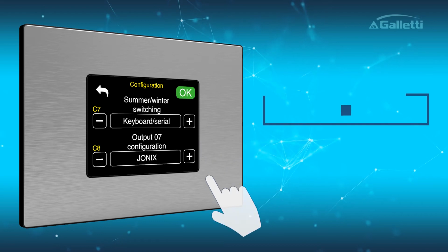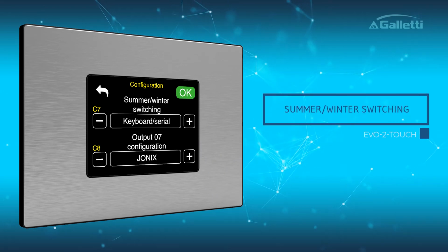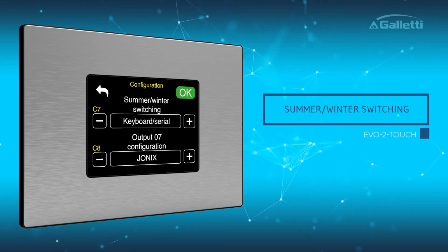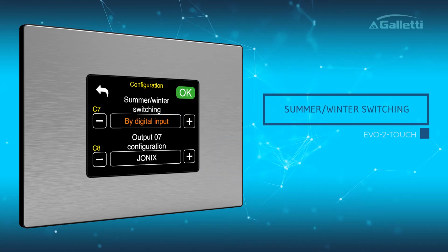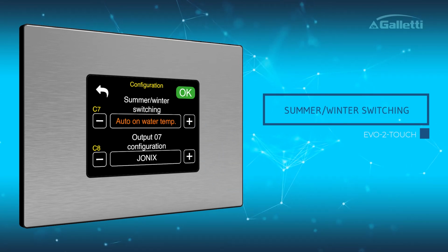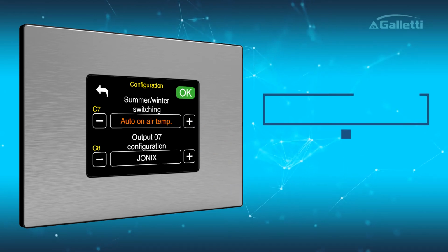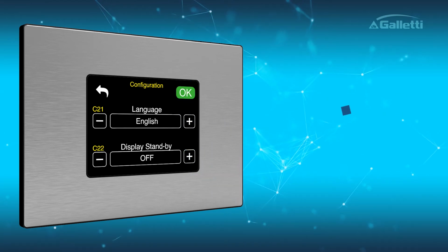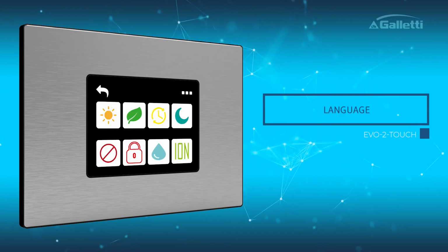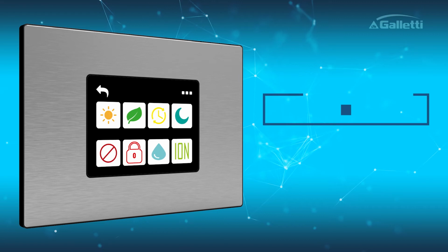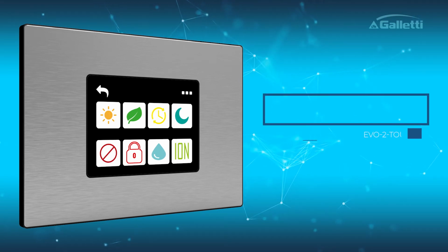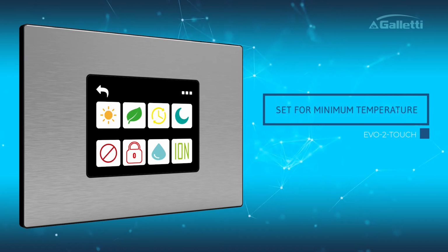To change the mode logic for seasonal operation, a wide choice of operating logics are available. Local mode, remote mode, which is made possible by digital input DI1, operating logics based on water or air temperature. By scrolling through the screens, it is also possible to change the language. The minimum temperature control function prevents, when the thermostat is off, the room temperature from falling below a threshold that can be set on the configuration screen.